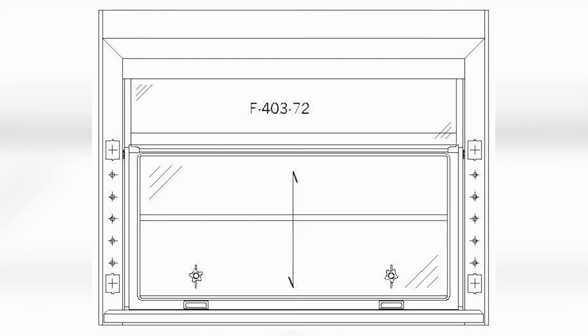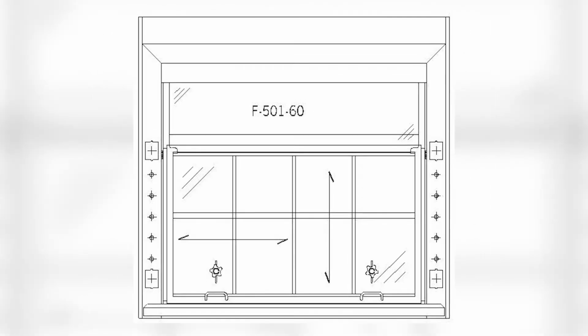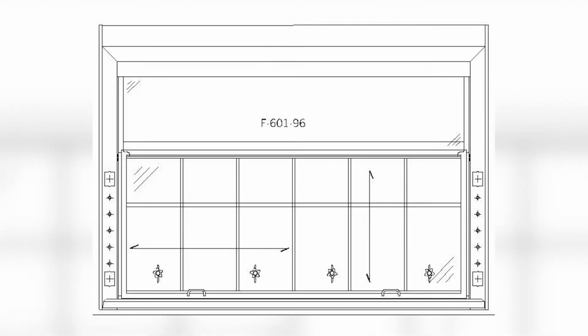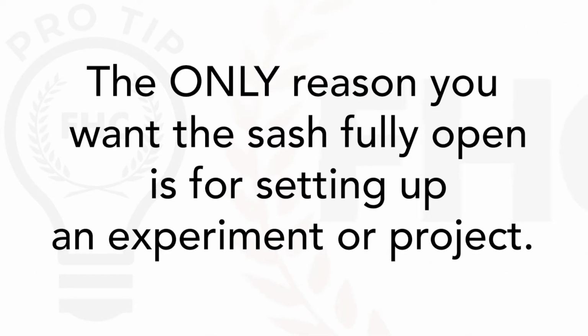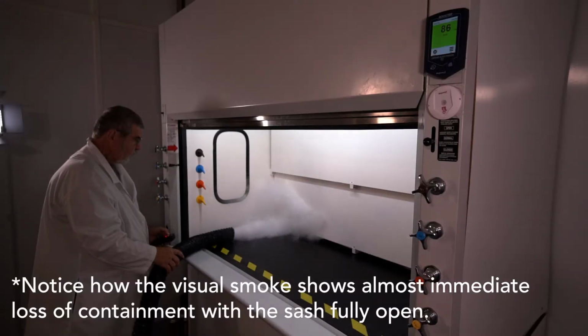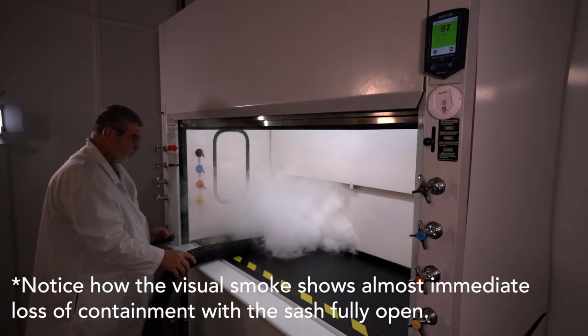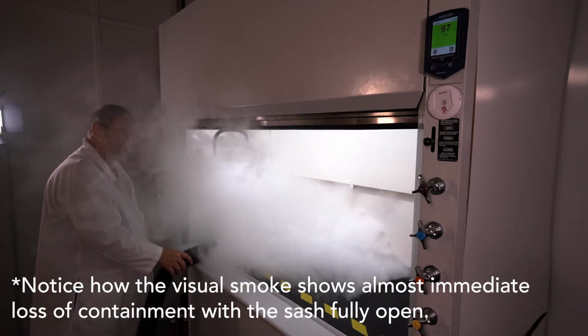The most common is vertical rising, which is a single sash glass that goes up and down like a window. And then there are combination or combo sashes, which have sliding panels that move left to right and that are inside a vertically rising frame. Regardless of the sash type, the only reason you want the sash fully open is for setup. A very common mistake is working with the fume hood in full open position. Lowering the sash is better.